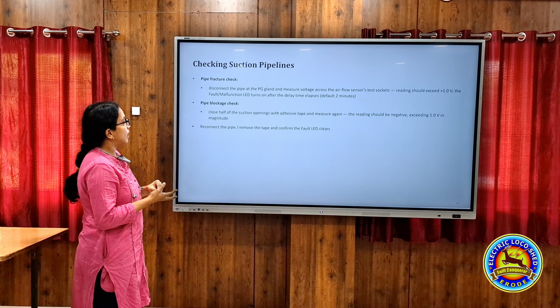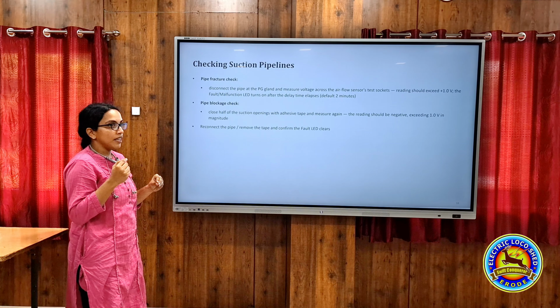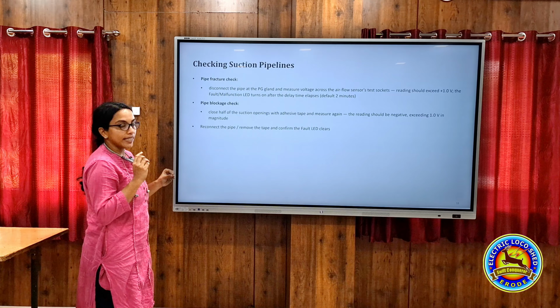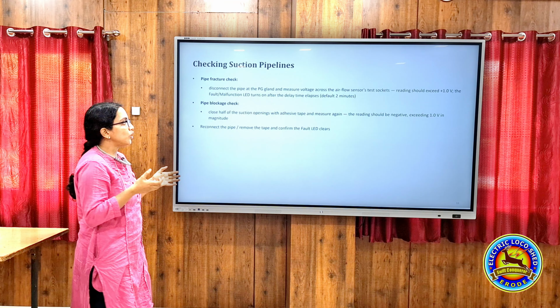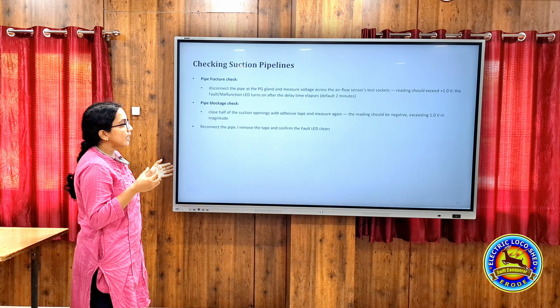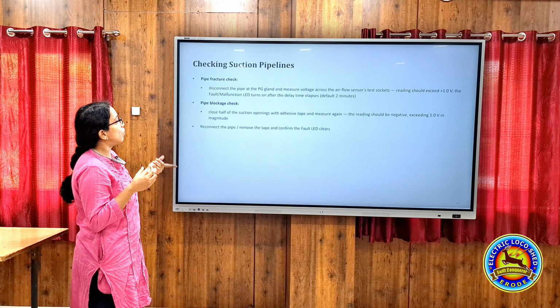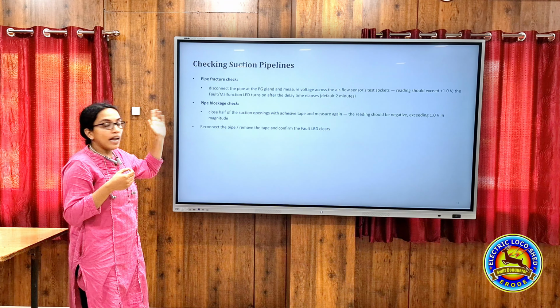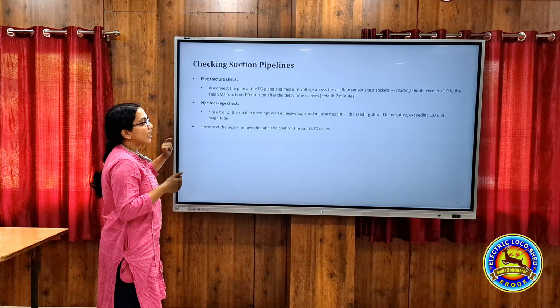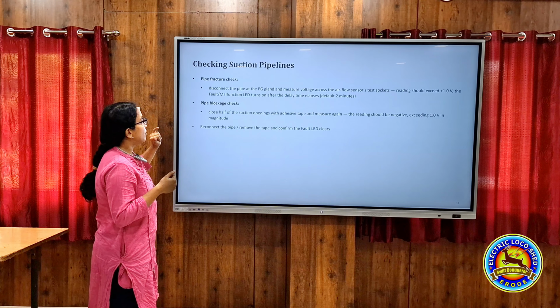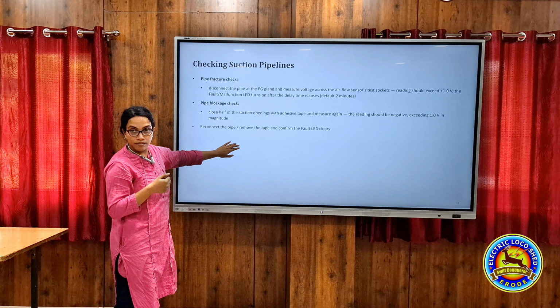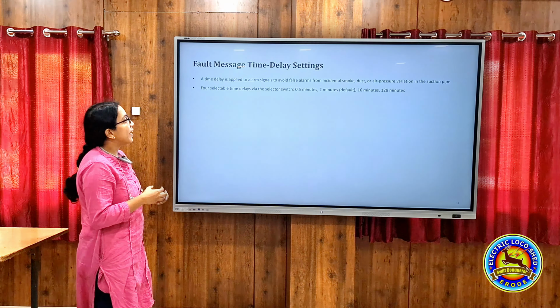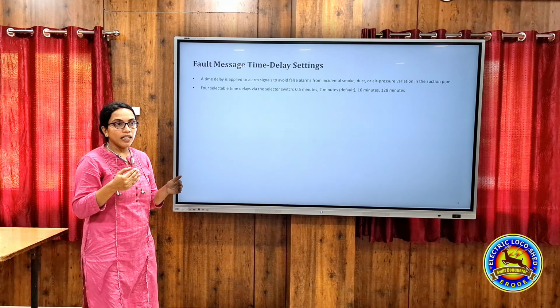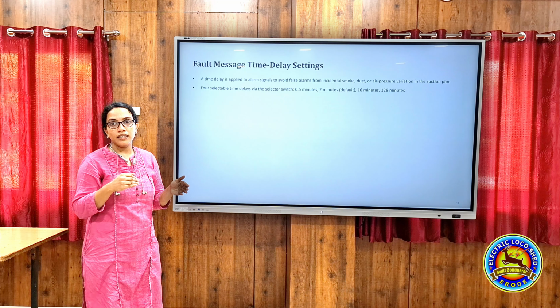In case of a pipe fracture, there will be an airflow sensor test socket across which the voltage will be greater than 1 volt if it is a fracture, and the voltage will be less than 1 volt if it's a blockage. And when a fault is detected, after a time delay of 2 minutes, using the time delay settings, we are transferring the fault to the VCU.